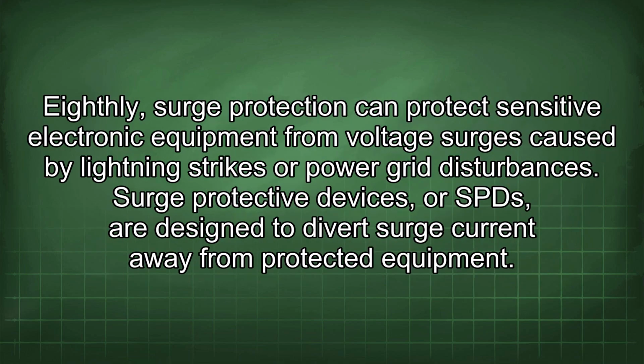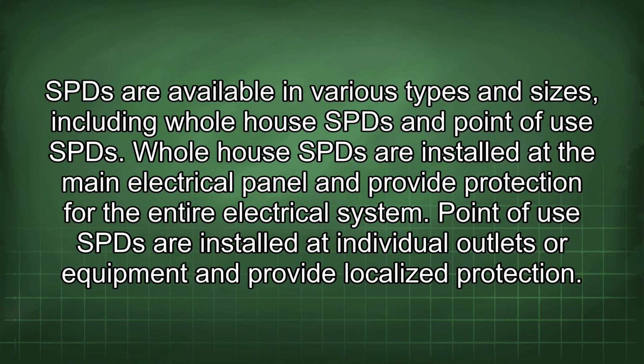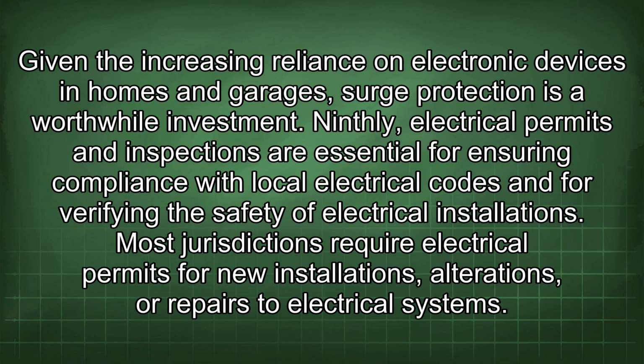Eighthly, surge protection can protect sensitive electronic equipment from voltage surges caused by lightning strikes or power grid disturbances. Surge protective devices, or SPDs, are designed to divert surge current away from protected equipment. SPDs are available in various types and sizes, including whole house SPDs and point-of-use SPDs. Whole house SPDs are installed at the main electrical panel and provide protection for the entire electrical system. Point-of-use SPDs are installed at individual outlets or equipment and provide localized protection. Given the increasing reliance on electronic devices in homes and garages, surge protection is a worthwhile investment.